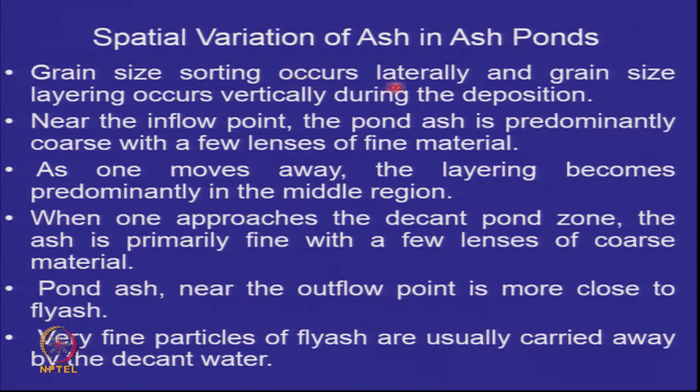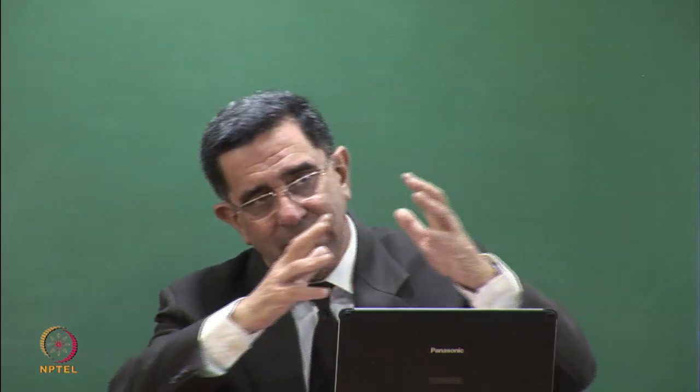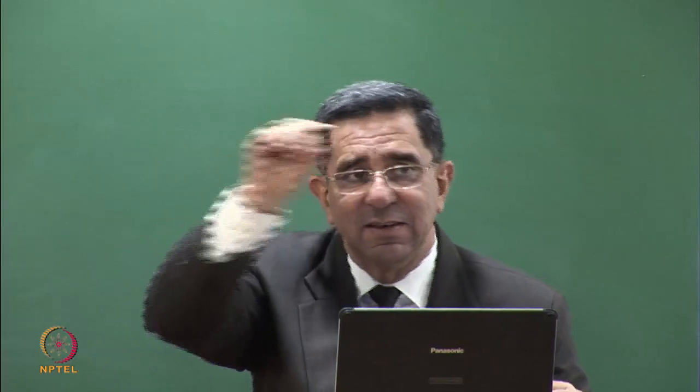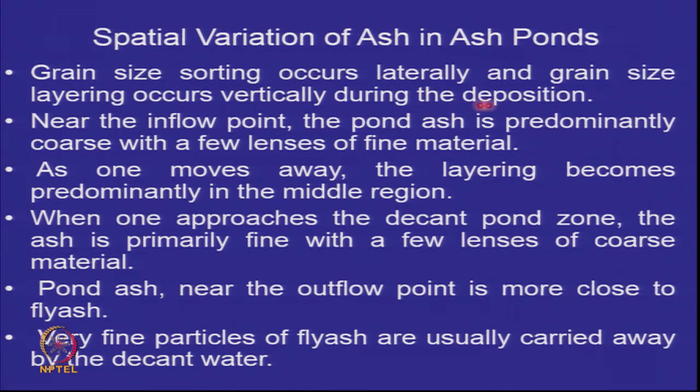There is spatial variation of ash in ash ponds: grain size sorting occurs laterally and grain size layering occurs vertically during deposition. Two things happen simultaneously: the slurry moves from inflow to outflow, with coarser particles settling first laterally, and within a single location, coarser particles settle first vertically — similar to what happens in the hydrometer test. So digging through ash reveals layers of coarse ash and fine ash, because coarse particles settle before fine ones with each load deposited.